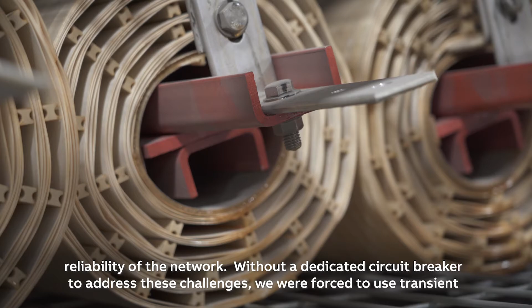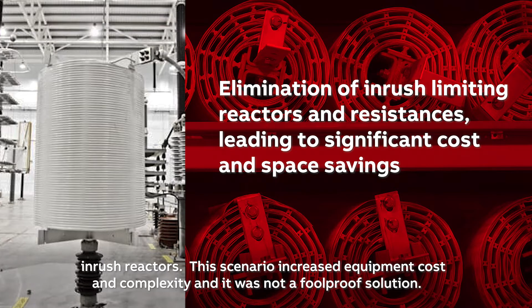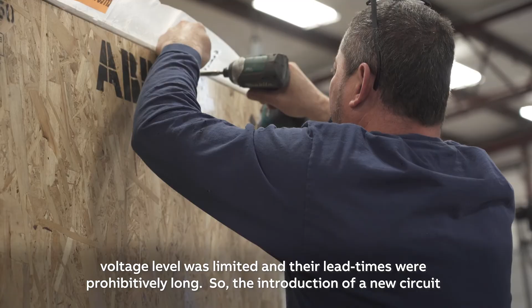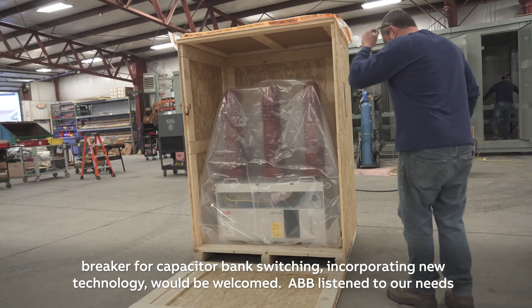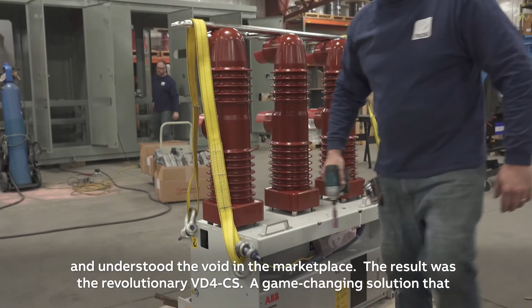Without a dedicated circuit breaker to address these challenges, we were forced to use transient inrush reactors. This scenario increased equipment costs and complexity, and it was not a foolproof solution. You see, in renewable power plants, we often have capacitor banks with switching requirements in excess of 15 megavars, and we have multi-stage systems exceeding 60 megavars. The number of vendors supplying switching devices at this voltage level was limited, and their lead times were prohibitively long. So the introduction of a new circuit breaker for capacitor bank switching, incorporating new technology, would be welcomed. ABB listened to our needs and understood the void in the marketplace.